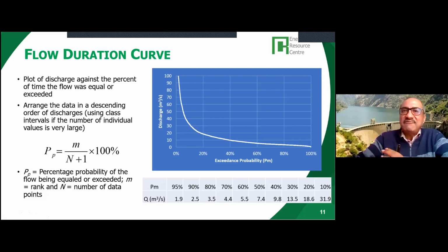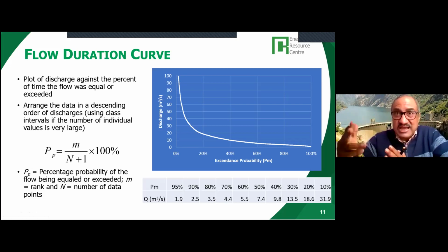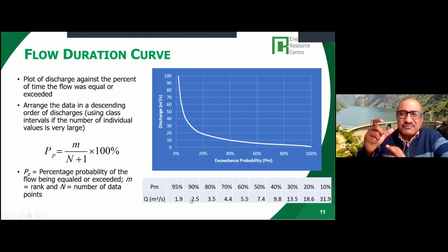But when you have, let's say, only 1.9, then you generate using just one turbine. So this is an optimization problem. But normally, when you design for 80%, 90%, or 95%, the number of turbines doesn't really make a difference because the flow variation is not much.